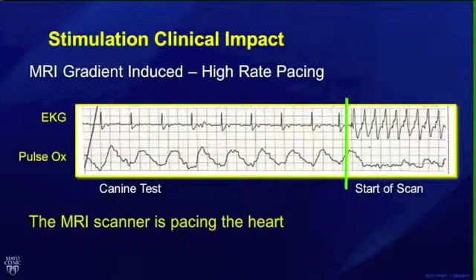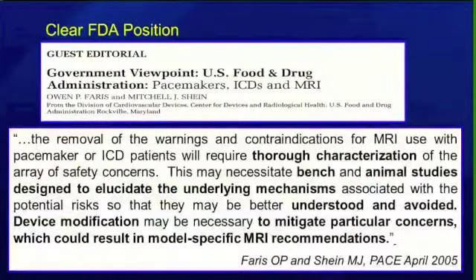And we have in the back of our mind the two classic conflicts. On the one hand, we know that in some situations we get clear untoward effects with various aspects of the MRI. If we go back a few years, about 8 years, there was a clear FDA position with strong language, as clear as it gets, that if you want to try doing this, you have to have bench testing, specific device testing, specific field testing, the MRI in your lab that you're going to use, and do it all over again every time the device changes, or when the MRI in your hospital changes.